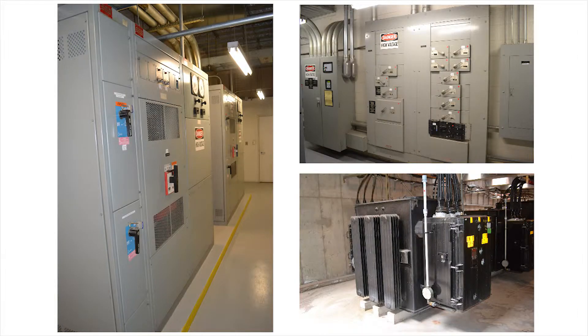It is important to realize that busway is not maintenance-free. It is electrical equipment, just like your main switchgear, your panel boards, and your transformers. Each type of electrical equipment, including busway, has recommended maintenance from its manufacturer.